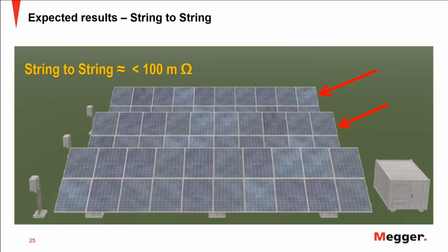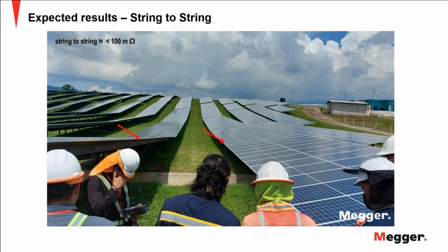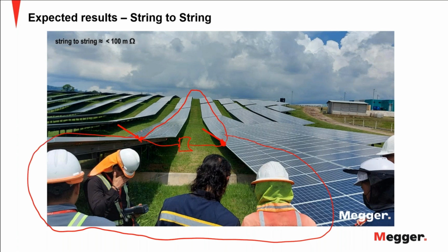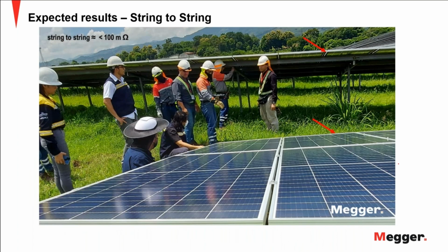And then you want to perform the measurement between the strings or between the racks, string to string or inter-rack. Basically you can do the test from this end to this end, or you could do it somewhere in the middle from this point to the other end here, and that's what we have here in the pictures. Here you don't need such long conductors. You're connecting a set of leads here, your instrument is in between, and then you have the other set of leads here. The current is going to go all the way down there and come back here, and the same here. It's going to come all the way and return, so it's going to be a parallel path for the current. But anyway, that's going to give you the calculation of that resistance.